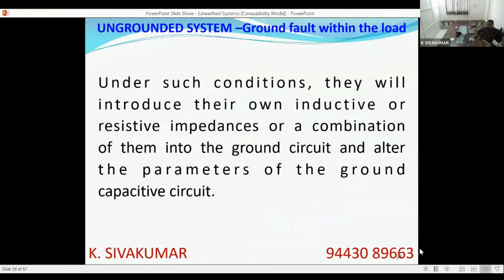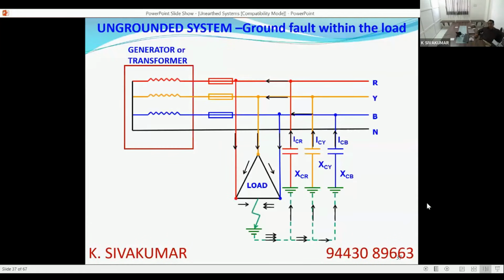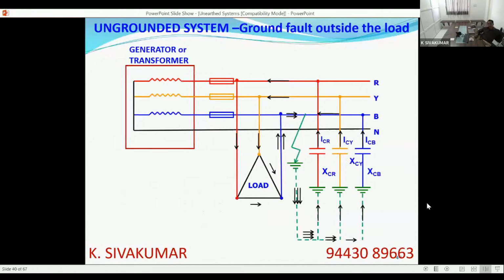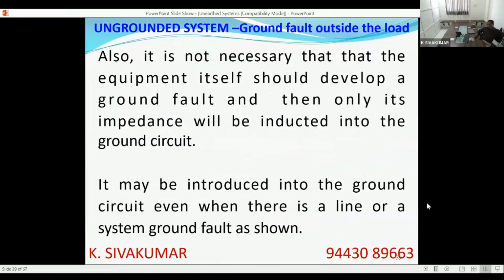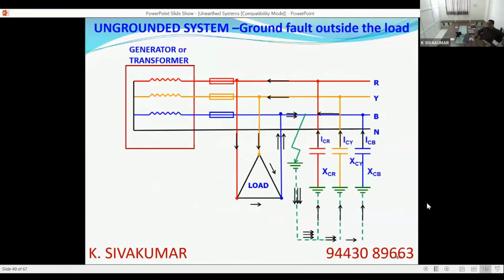Now, under such conditions, they will introduce their own inductive or resistive impedance or a combination of them into the ground circuit. Now it is no more only capacitive current. It will be a mixture. It will be a series circuit of R and C or XL and XC or R, XL, XC circuit depending upon the proportion of the components. Moreover, it need not be that the fault happens inside the load or the source. Even if there is any system fault in the network, the impedance will be introduced into the ground circuit like this.